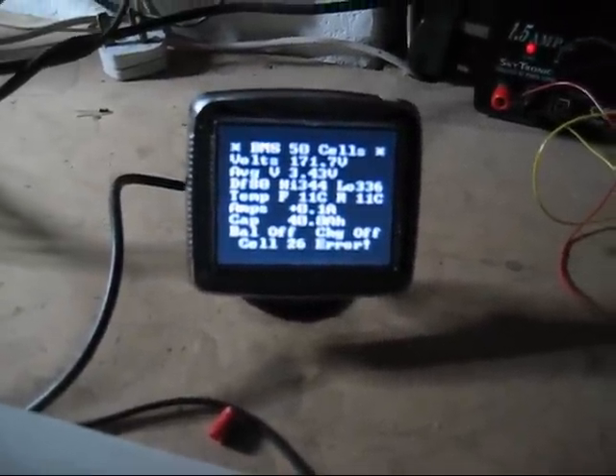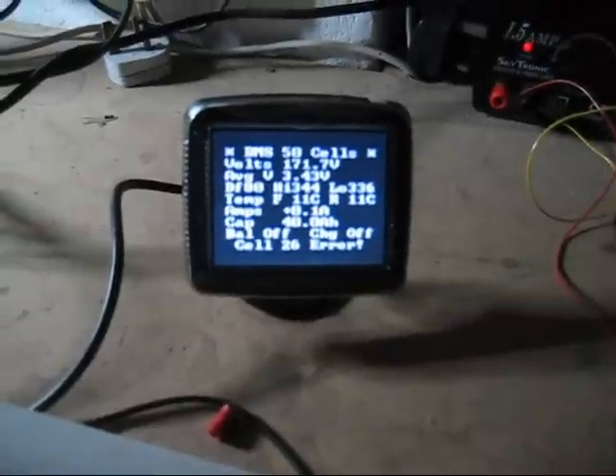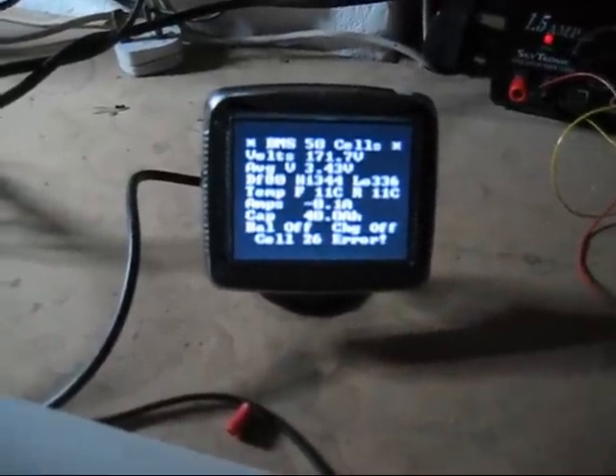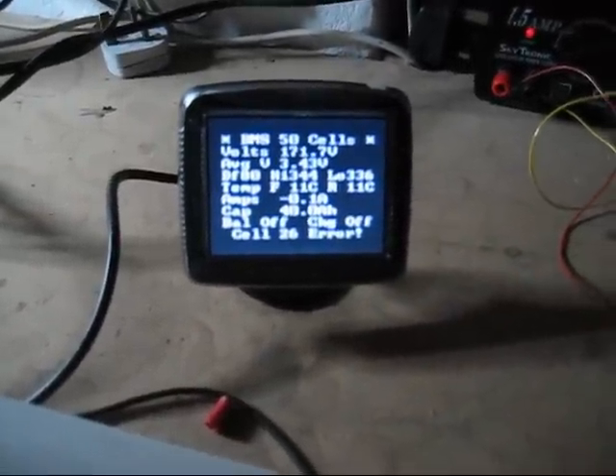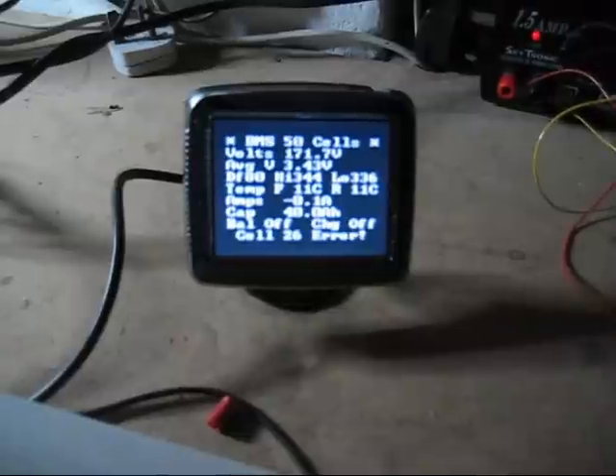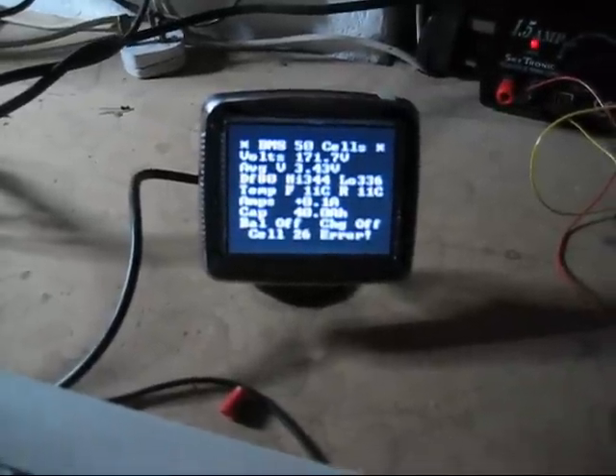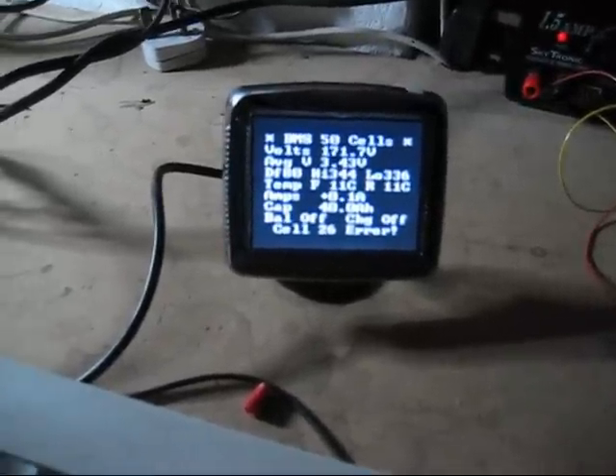You can see it's immediately indicating an error with cell 26. It's the first one in the second pack, and you can probably hear the tone in the background indicating an error.